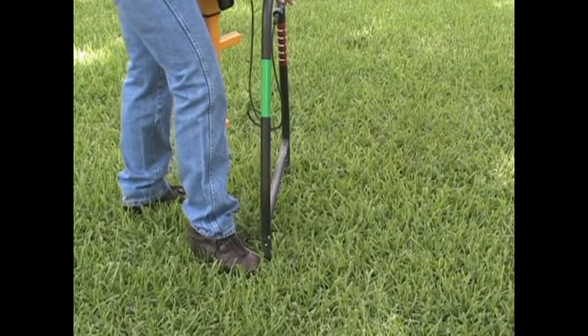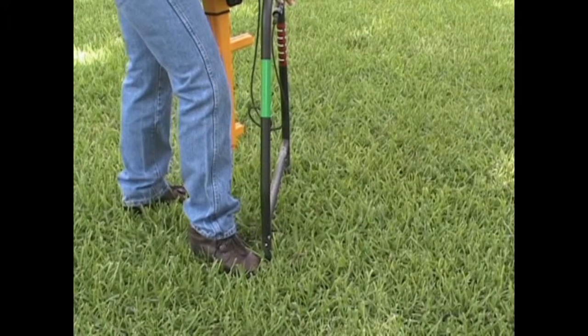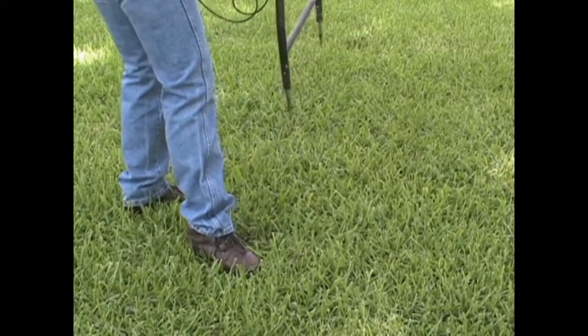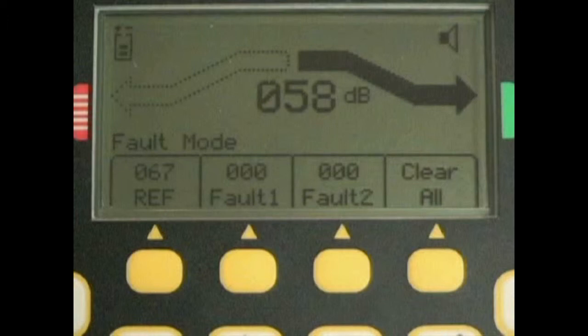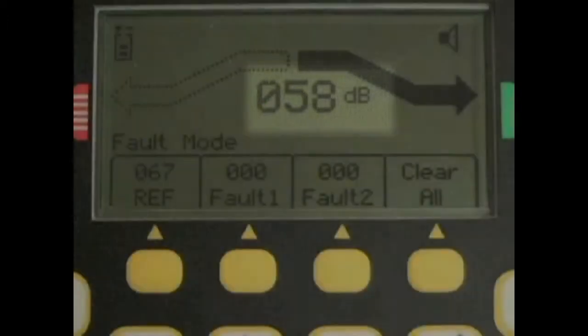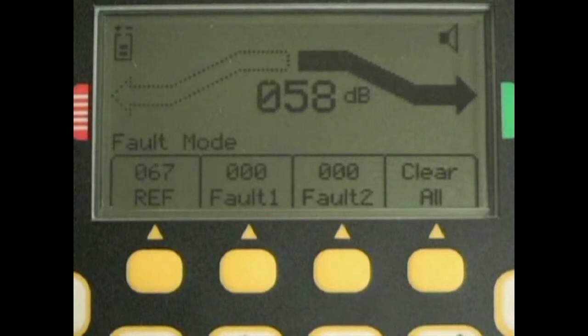After the fault has been found, move the A-frame about one frame width away from the fault and insert it into the ground with the green leg toward the fault. Note the signal level on the receiver screen. If this is the only fault on the line, or the most severe fault on the line, the numerical signal strength on the receiver screen will measure within 12 dB of the reference reading you took at the ground rod. This reference reading is in the bottom left corner of the screen, labeled REF for reference.